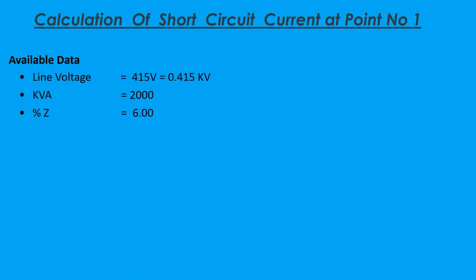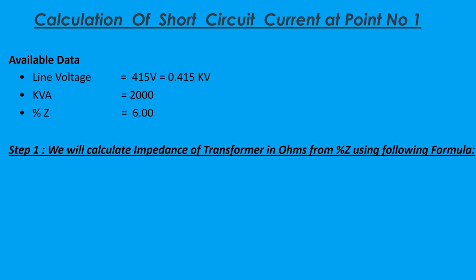For calculation of short circuit current at point number one, the available data is: line voltage equals 415 volts, that's 0.415 kilovolts, kVA is 2000, and the percentage impedance is 6%. Step one: we'll calculate the impedance of the transformer in ohms from percent impedance using the formula — impedance of transformer equals percentage Z times 10 times kV squared, all divided by kVA.